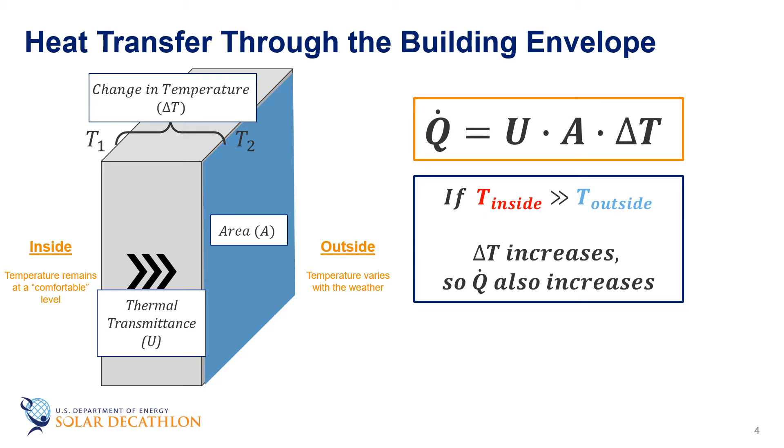Thinking about this on a bigger scale, colder climates have larger delta T's compared to mild climates. In these colder climates or in the winter when you generally have a larger delta T, a common strategy is to reduce the inside temperature in order to reduce the delta T from inside to outside. This is often called a temperature setback.